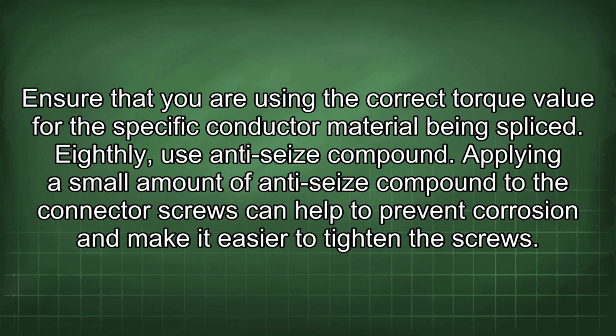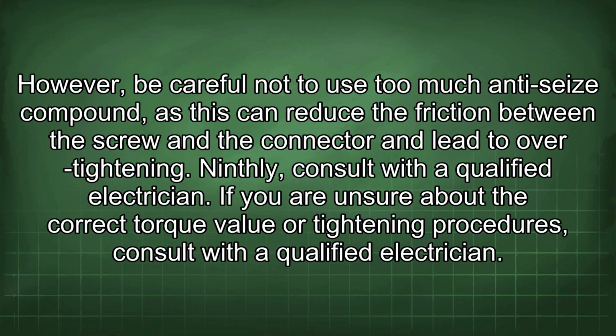Eighthly, use anti-seize compound. Applying a small amount of anti-seize compound to the connector screws can help to prevent corrosion and make it easier to tighten the screws. However, be careful not to use too much anti-seize compound, as this can reduce the friction between the screw and the connector and lead to over-tightening.